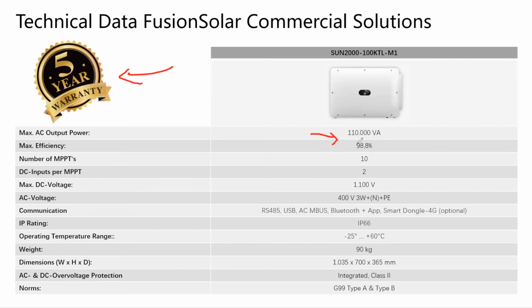Maximum AC output power is 110 kilowatts. So this is the apparent power. At a power factor of 1 it can output the same power. I reiterate, 10 MPPTs, 20 strings in total, maximum DC input 1,100 volts, 90 kilograms, it's IP66, and communication with the monitoring platform is also done with the 4G dongle, or you can use another device which is called the smart logger. We have some presentation slides for these devices as well.